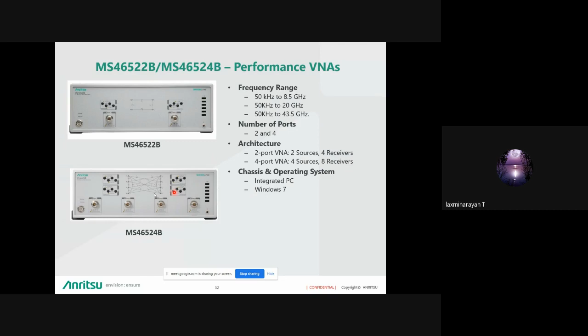So this is a 522B and 524B, which starts from 50 kilohertz to 8.5, 20 and 43.5 gigahertz. We have both the combinations, a 2-port and a 4-port solution. It has 2 sources in the 2-port with 4 receivers, and 4 sources in the 4-port with 8 receivers, which is integrated with Windows 7 and a PC also. We just need an external monitor to display the VNA. And it has the industry's best 140 dB dynamic range with a maximum output power of minus 32 to plus 10 dBm, and a fast sweeping speed of 130 microseconds, and the performance at a lower price.